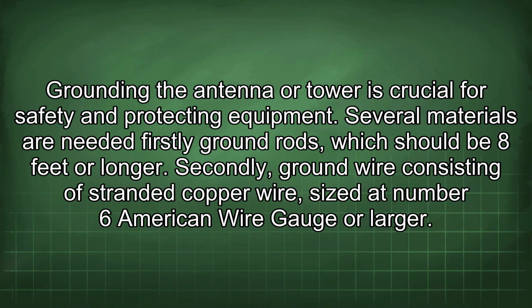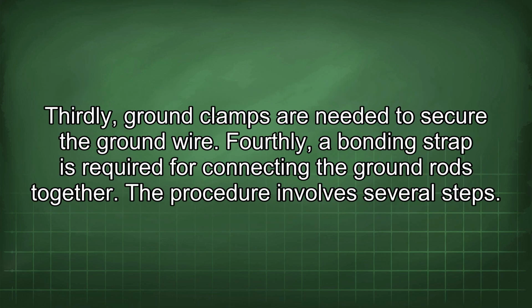Grounding the antenna or tower is crucial for safety and protecting equipment. Several materials are needed. Firstly, ground rods, which should be 8 feet or longer. Secondly, ground wire consisting of stranded copper wire, sized at number 6 American wire gauge or larger. Thirdly, ground clamps are needed to secure the ground wire. Fourthly, a bonding strap is required for connecting the ground rods together.